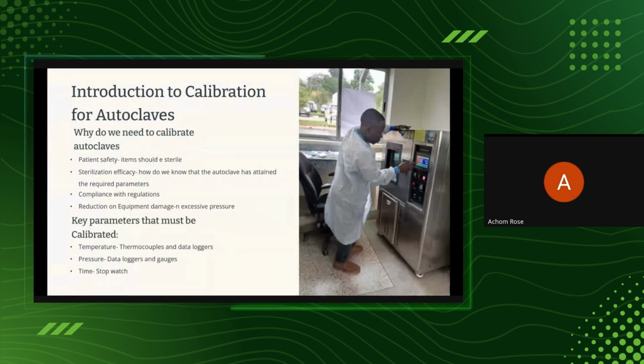Then we have another parameter, which is the pressure. For pressure, we also have the best one, the data logger. We are doing the key parameters that we must be calibrating. I mentioned the temperature and the pressure. So for pressure, like I mentioned, it's the data loggers that give us accurate results because the equipment is running, so you don't want to stop. However, sometimes you may want to calibrate the gauge to be sure that the gauge is giving you the right reading, the right indication of what is inside. So you're able to calibrate the pressure gauge. When you're calibrating the pressure gauge, you also need a standard gauge to calibrate the gauges.